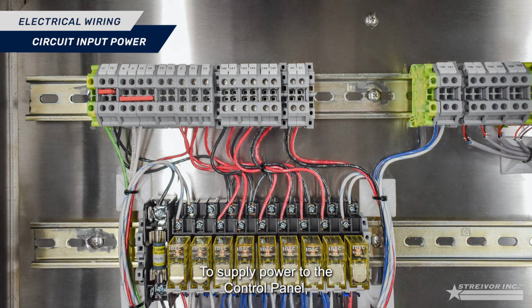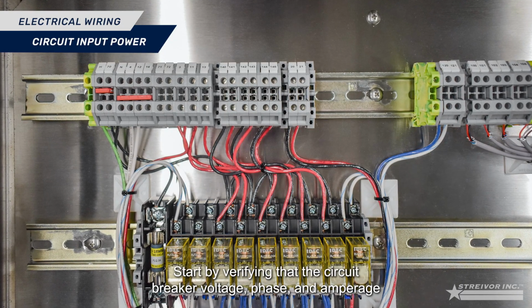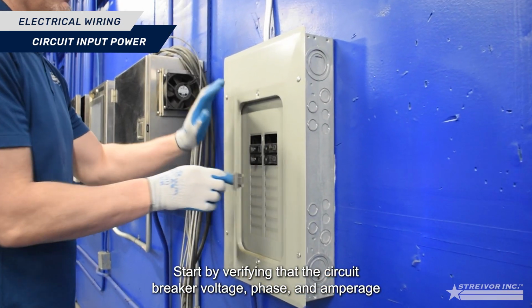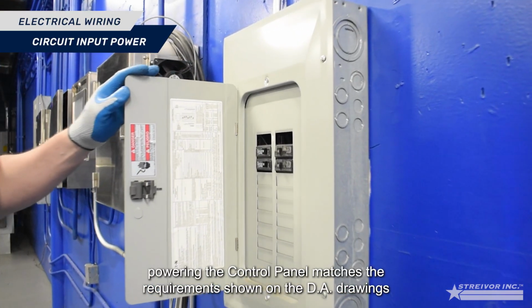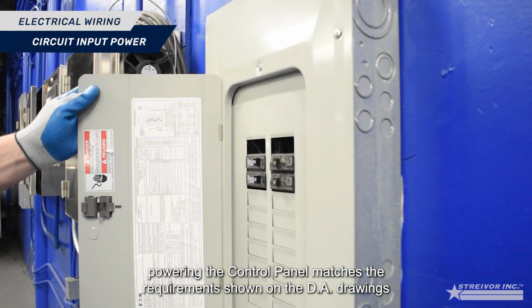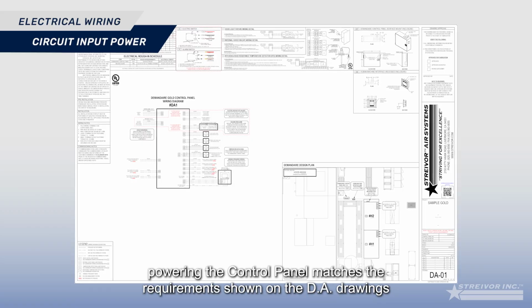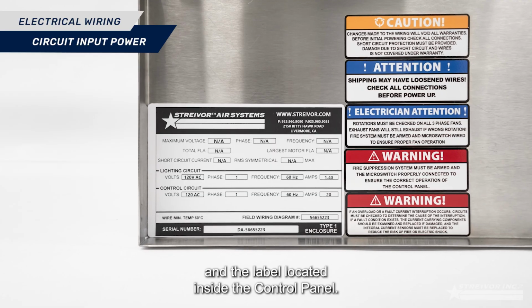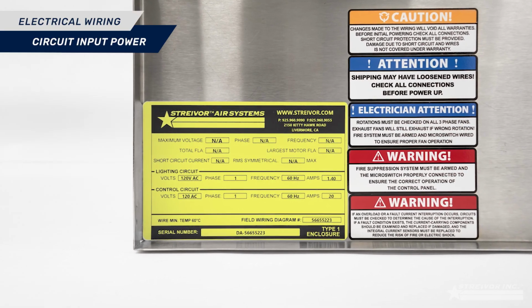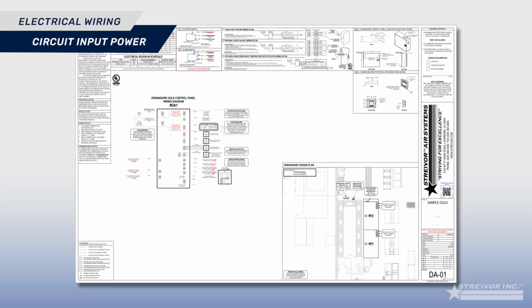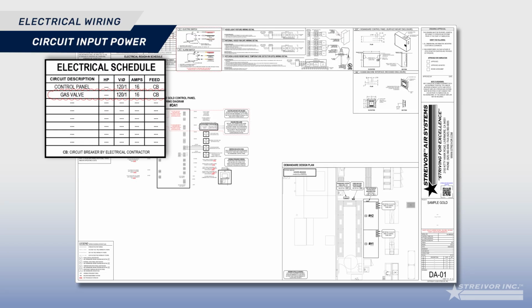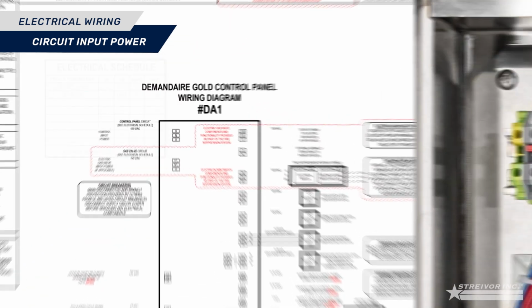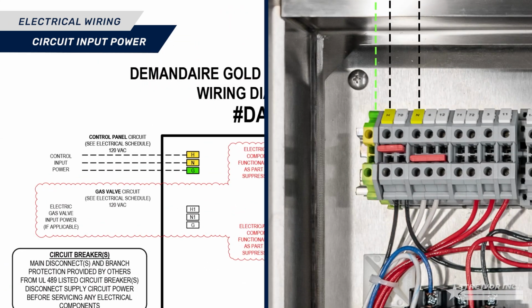To supply power to the control panel, start by verifying that the circuit breaker voltage, phase, and amperage powering the control panel match the requirements shown on the DA drawings and the label located inside the control panel. After verifying the circuit breaker is the correct voltage, phase, and amperage, proceed to connect the 120 VAC single-phase power to the designated terminal blocks in the control panel.